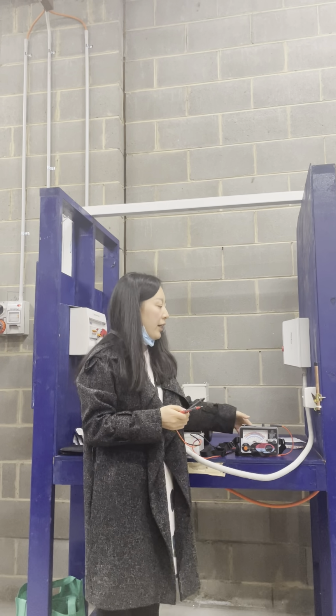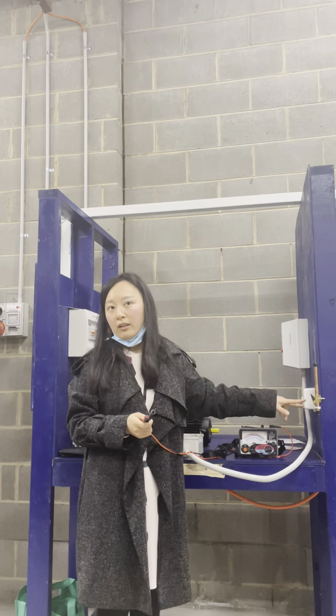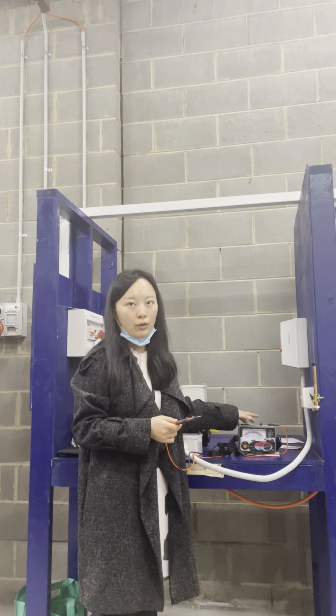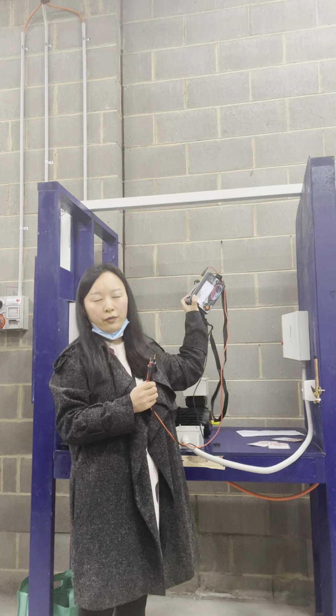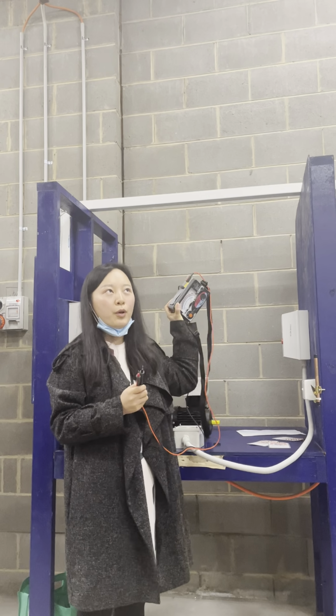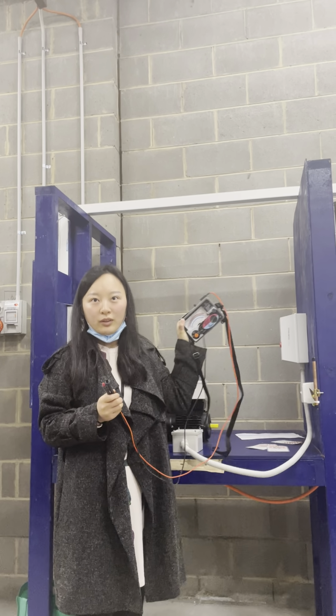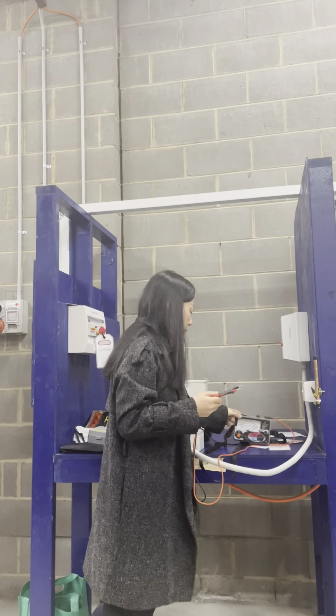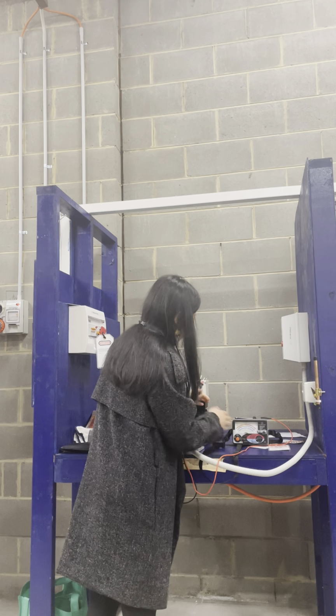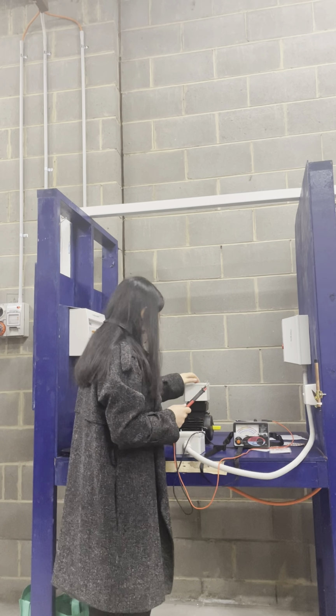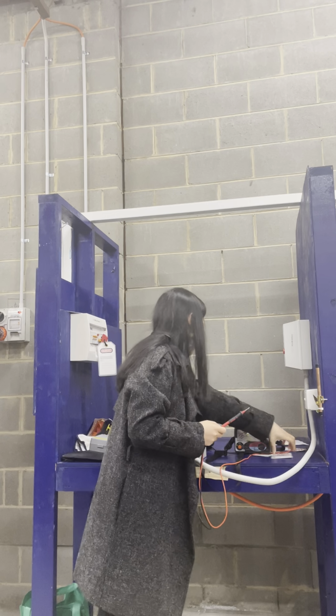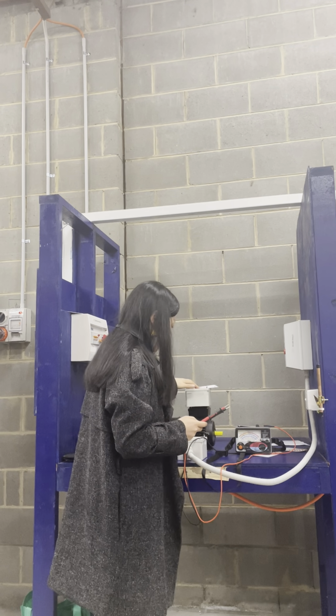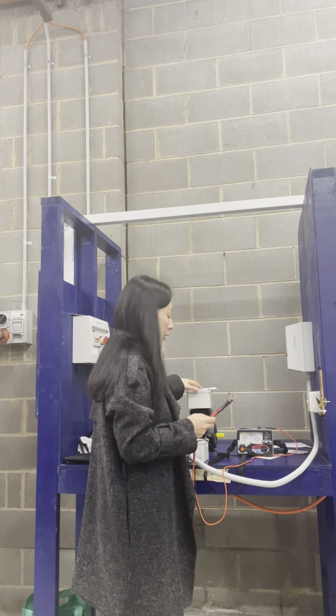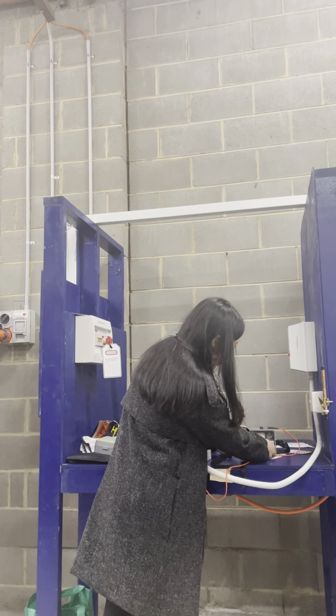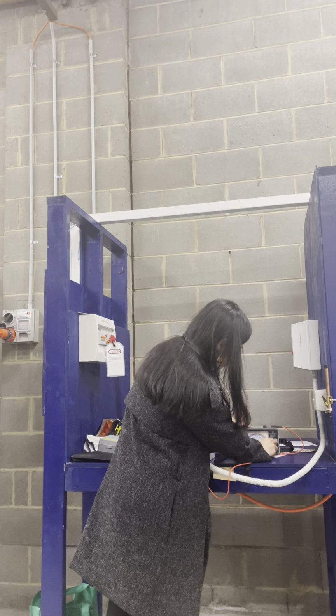So it doesn't matter reconnection or disconnection. To check the earth is always the first thing to do, and this is always the first device you will touch. Just remember, this is your device. Okay, so the next thing is, this is a brand new motor. So place the danger tag first, if it wasn't removed. Okay, now the first test you need to do is an IR test.